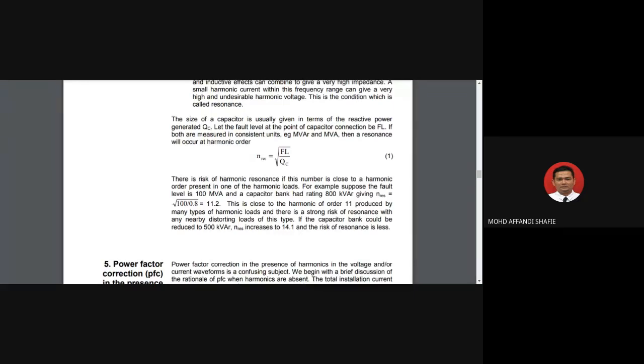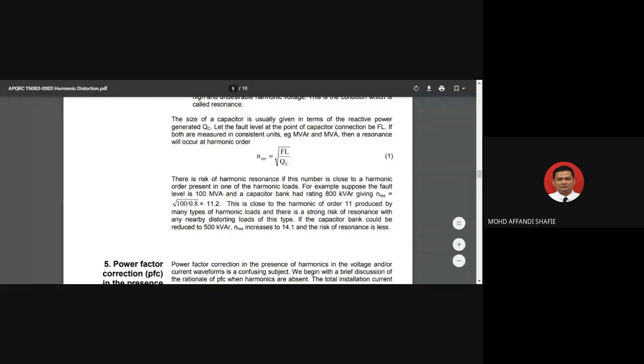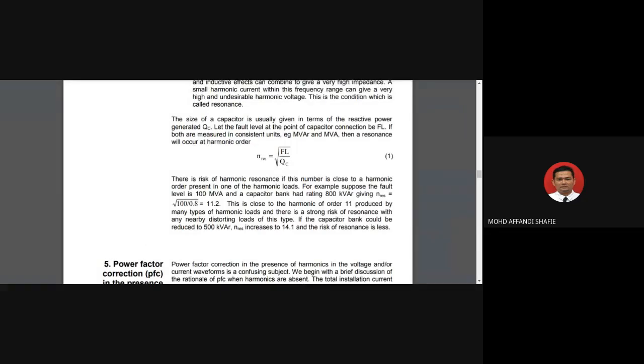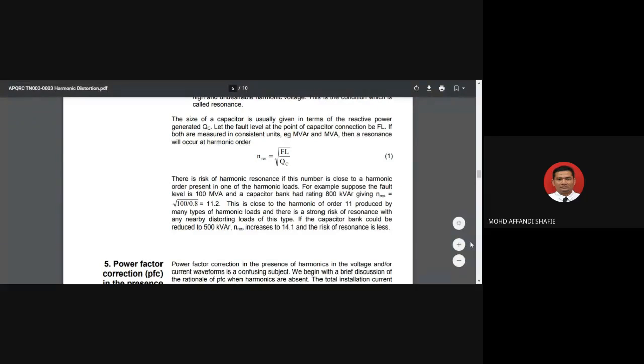So for example, suppose the fault level is 100 MVA and a capacitor bank had rating 800 kVAR, giving N_R equal to the square root of 100 divided by 0.8, equal to 11.2. So this is close to the harmonic of order 11 produced by many types of harmonic loads, and there is a strong risk of resonance with any nearby distorted load of this type. So if the capacitor bank could be reduced to 500 kVAR, the resonance would increase to 14.1, okay, 14.1, and the risk of resonance is less. So this is how we calculate the resonance here.